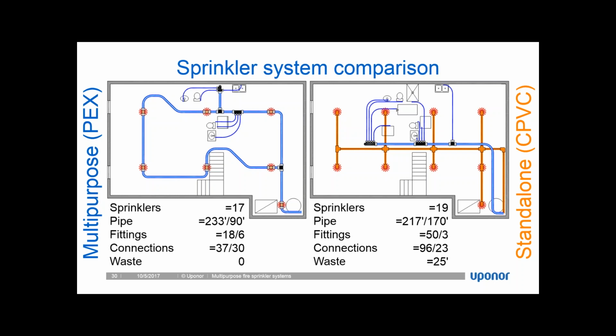All right. We do have a question from Oren wanting to know if this is going to work in 6 to 8 unit multifamily dwellings. Okay, yeah. Good question, and I have to make some assumptions here. When we're talking about 6 to 8 unit multifamily dwellings, they have to be configured like a townhouse. And townhouses have specific limitations in NFPA 13D, the standard that governs the installation of 1 and 2 family dwellings in townhouses. They have to be open from the slab to the underside of the roof. So I can't have stacked units.